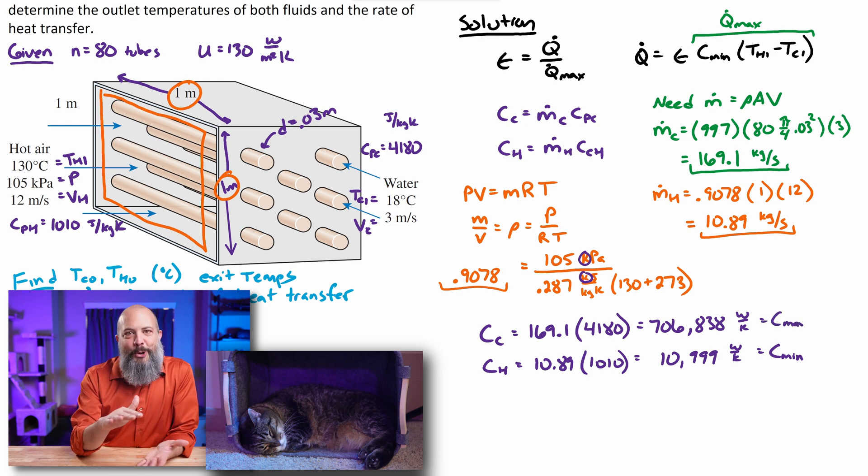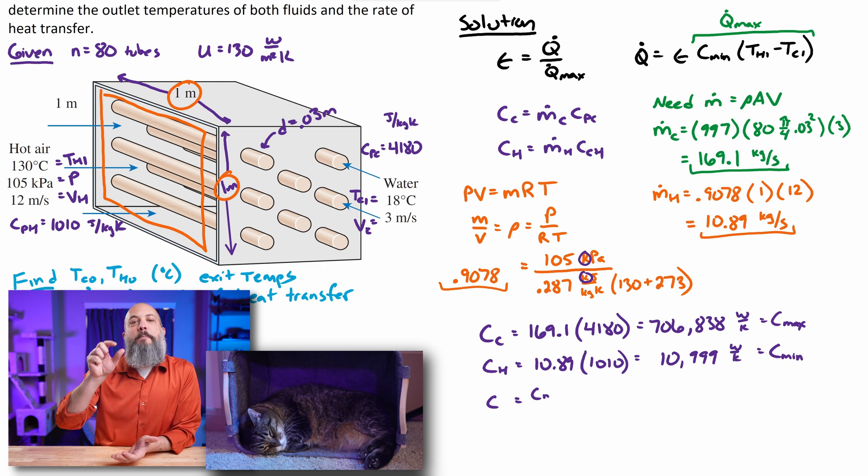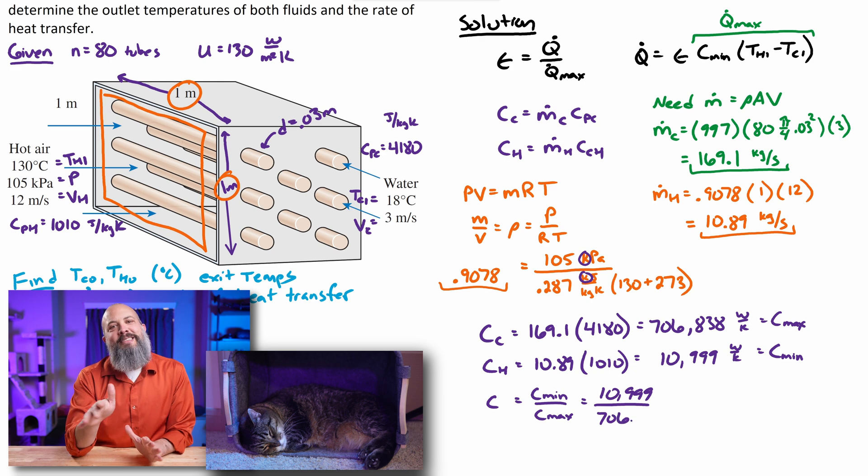So the 11,000 is going to be the minimum value for capital C, 706,000, the maximum value for capital C. The ratio between those two, either just capital C by itself, you might also call this CR for heat capacity ratio. The minimum C divided by maximum C, the 11,000 divided by 706,000. 0.01556 is capital C, also sometimes called CR, heat capacity ratio.